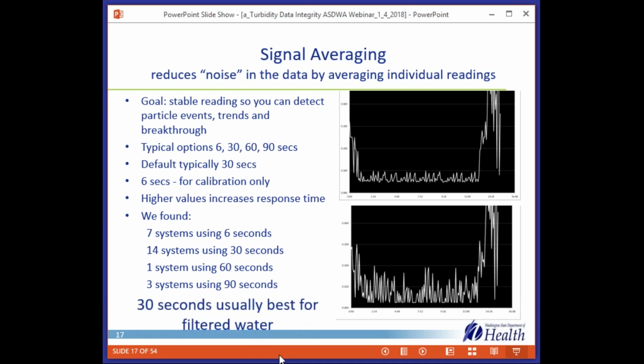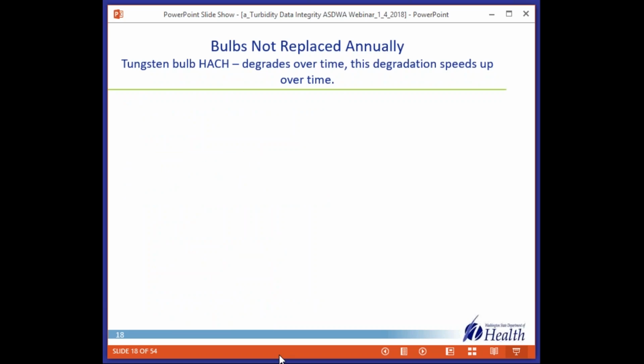So we think the default value of 30 seconds is a good starting place for filtered water, and it seems to work well for most plants in our state. Another interesting thing about this is that this does impact the value that's shown on the controller screen. So if you're looking at a device and you see a lot of erratic readings, the first thing I would check is the signal averaging setting.